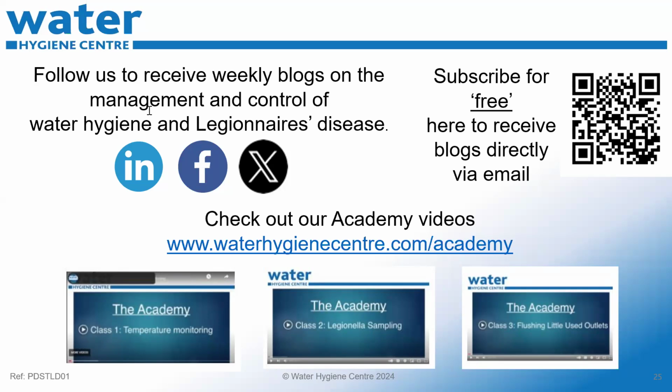Excellent, thank you. I'm going to take the last three questions then. So Ben has asked, do flexi hose fittings to filling loops, etc., increase the risk of increased Legionella bacteria? Yeah, flexi hoses have been a questionable item over the last few years, and that's because a study was done on them from removing them, opening them up, looking at the internals of these flexible hoses and swabbing those flexible hoses. And the internals of the flexible hose is rubber, and rubber is a fantastic organic material where biofilm likes to form because it's porous. It's got all these holes, nooks, crevices, etc. And this is where bacteria likes to form.